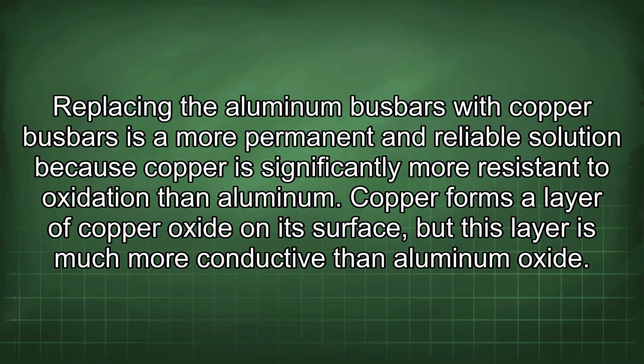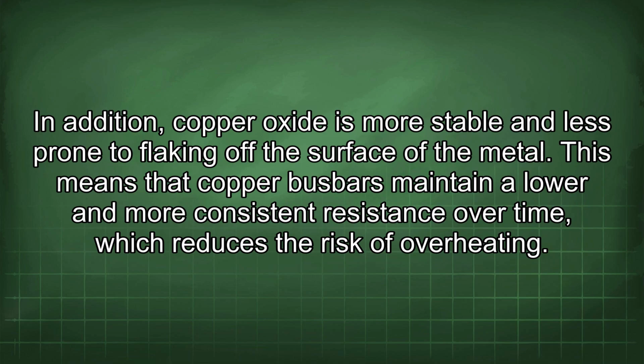Replacing the aluminum busbars with copper busbars is a more permanent and reliable solution because copper is significantly more resistant to oxidation than aluminum. Copper forms a layer of copper oxide on its surface, but this layer is much more conductive than aluminum oxide. In addition, copper oxide is more stable and less prone to flaking off the surface of the metal. This means that copper busbars maintain a lower and more consistent resistance over time, which reduces the risk of overheating.